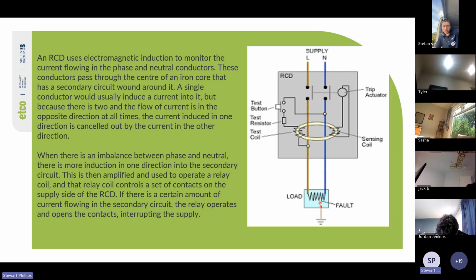Cool. So it uses electromagnetic induction to monitor the current flowing in the phase and neutral conductors that pass through the center of an iron core that has a secondary circuit around it. A single conductor would usually induce a current in it, but because the two are opposing each other, they cancel each other out. So when there's an imbalance between phase and neutral, current flows, a magnetic field is induced in the toroidal coil, activating the sensing coil and activating the trip actuator.